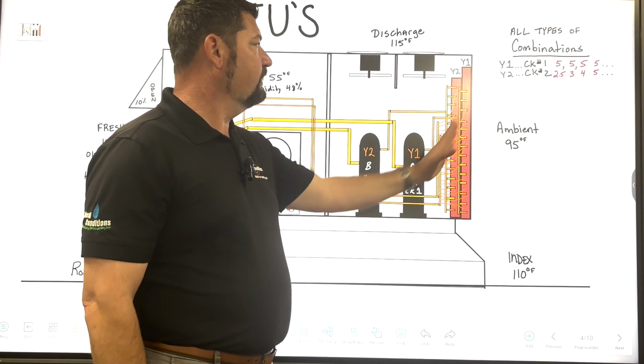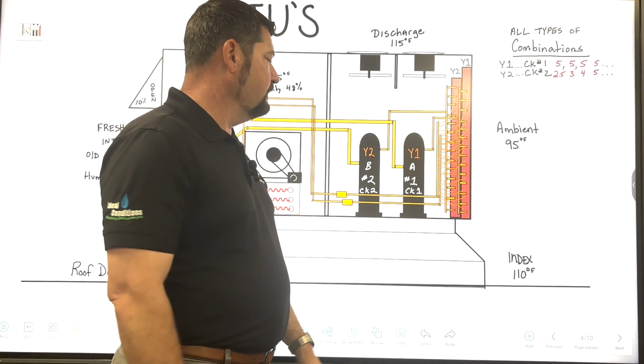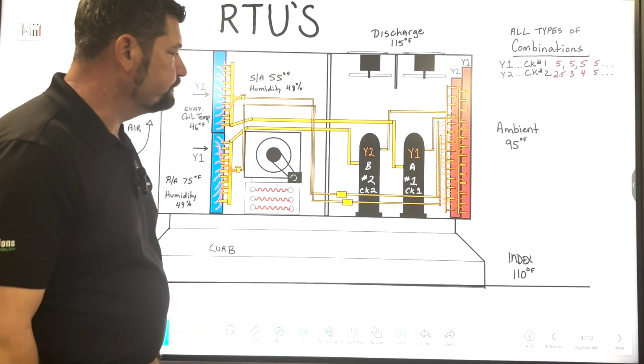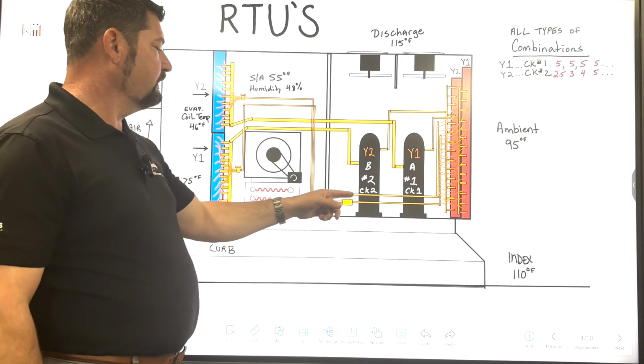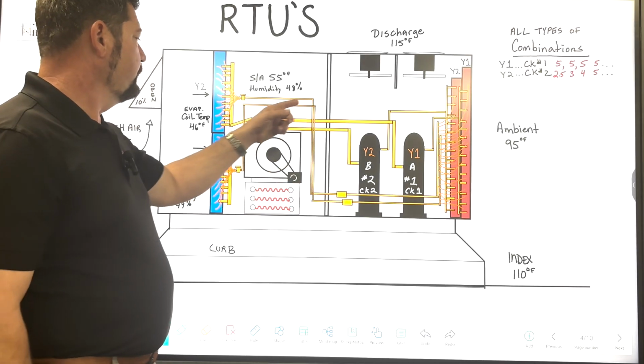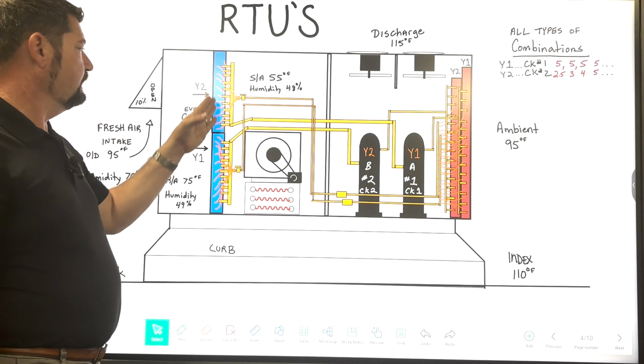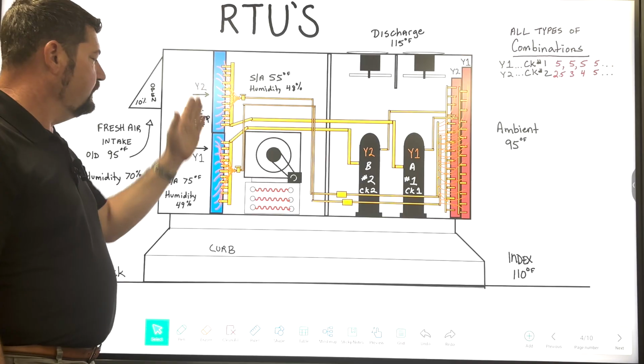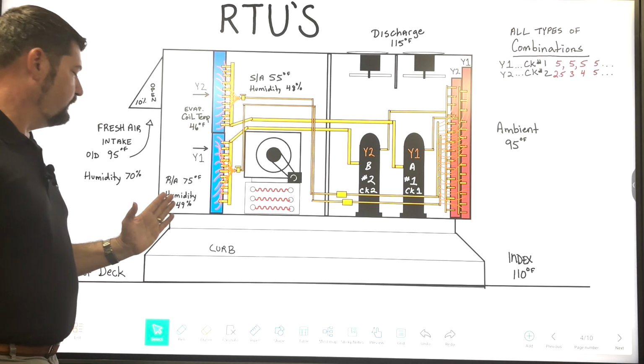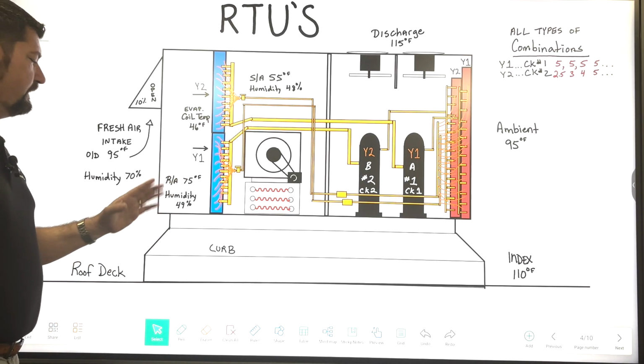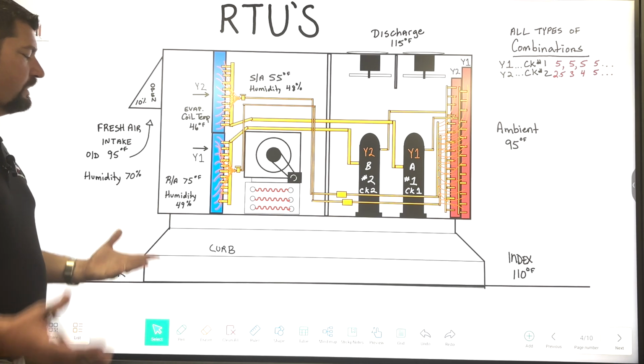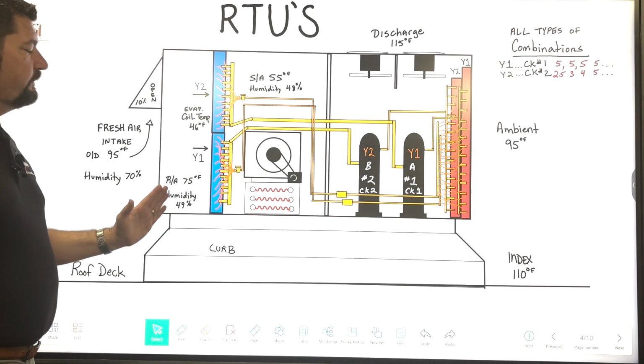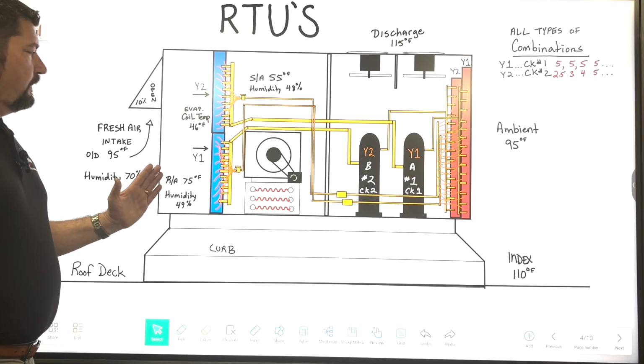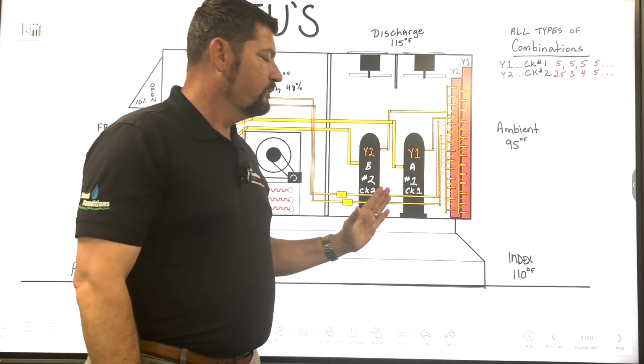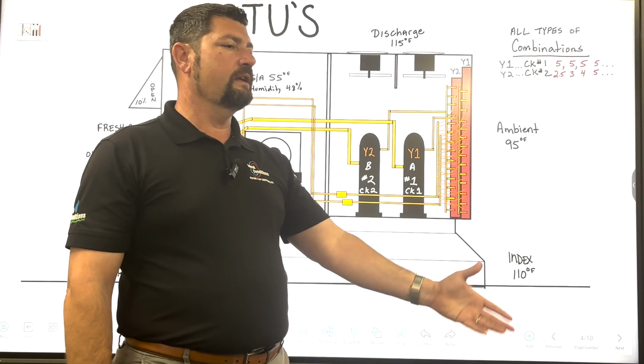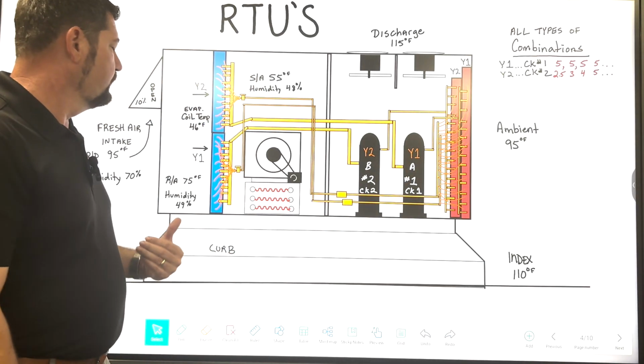As you cool that down, that heat is rejected out the top of that unit through your fans. And as a result of that, you'll have liquid running through the liquid line, and then that will meter, and that liquid will go into your evaporator coil, creating a cold coil. Here I put down that the return air was 75 degrees in my diagram, humidity at 49% roughly. And then of course, the longer you run, the lower the humidity in the building, the shorter the cycle, the higher the humidity.